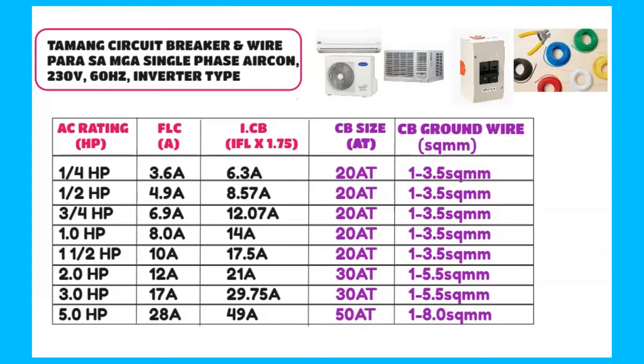To summarize our data based sa kanina, so meron tayong 20 ampere trip from 1/4 HP until sa 1 1/2, and then yung corresponding ground wire niya is isang 3.5 square mm, and then 30 ampere trip from 2 to 3 HP, and then yung grounding wire niya is isang 5.5 square mm, and then sa 5.0 meron tayong 50 ampere trip, and then yung grounding niya in-upgrade natin to 8.0 square mm. So next is, let's size na naman, ano yung maging size ng wire sa line to line.